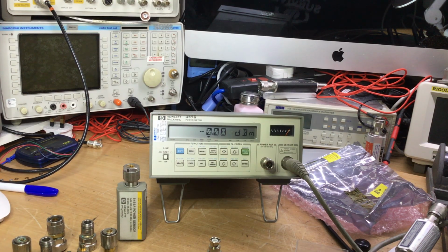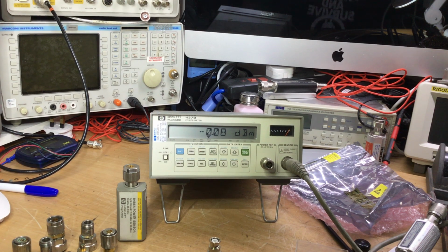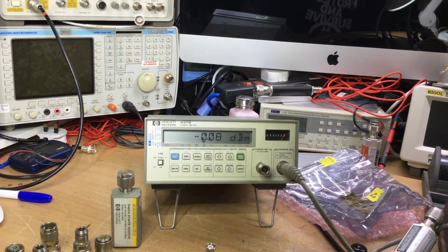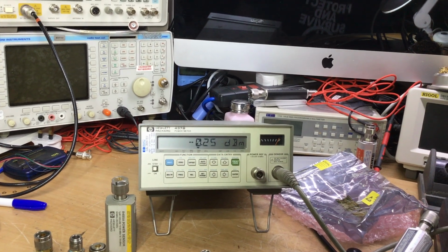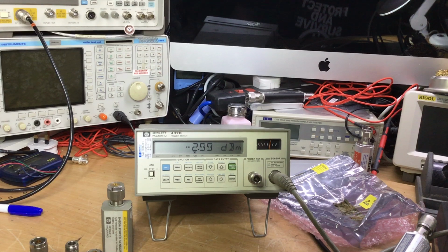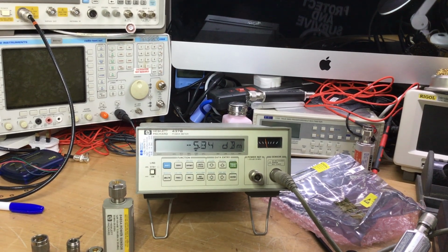Okay, so we are now generating an RF frequency sweeping right the way up to 26.5 gigahertz, and it's doing a slow sweep because I've reduced the sweep time. But as we can see, the accuracy at the meter is very good indeed there, and proves the sensor's working. Obviously, if I change the output power, so I'll just change the variable. Let's have a look now, get it right the way down here to a lower level just for demonstration purposes.